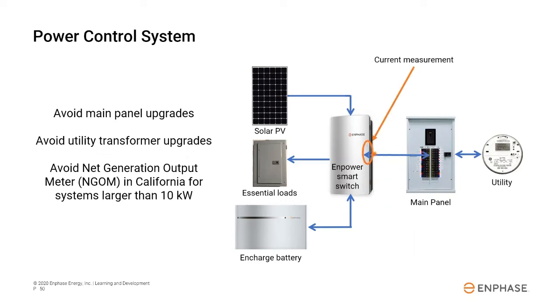PCS works by measuring electrical current flowing from the storage system to the main service panel in real time, and then precisely controlling and limiting the current to a pre-configured safe level. When using PCS, when you do the NEC 120% rule calculation, you only need to account for the PV backfeed and not the storage backfeed. So this can allow you to actually install a small solar and battery storage system on a 100 amp service panel, which would normally not be allowed.